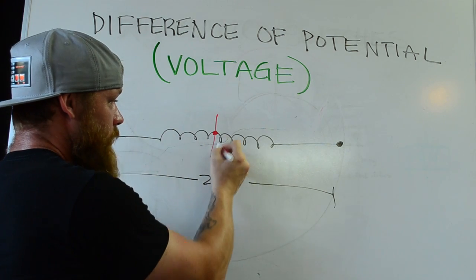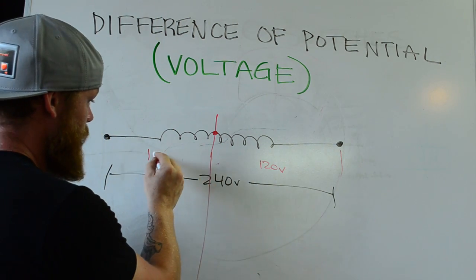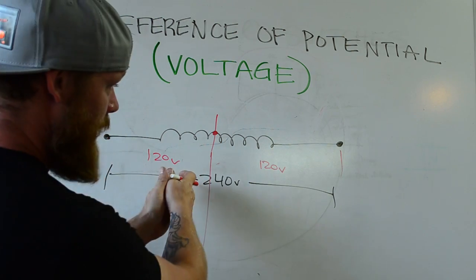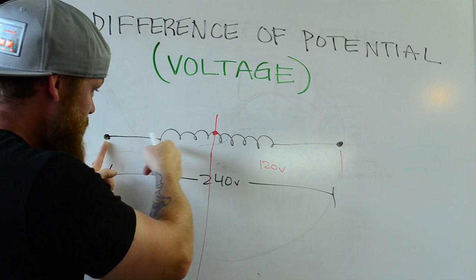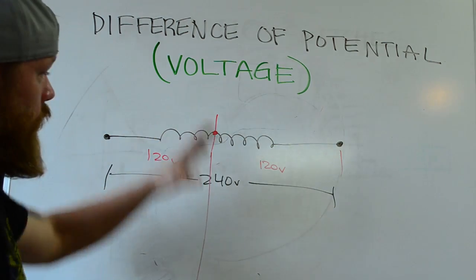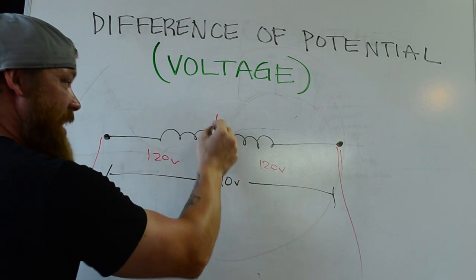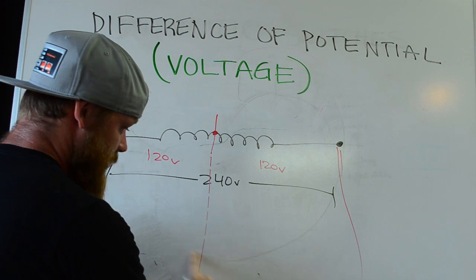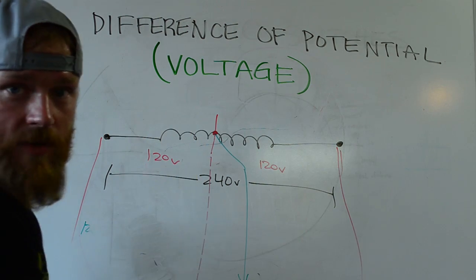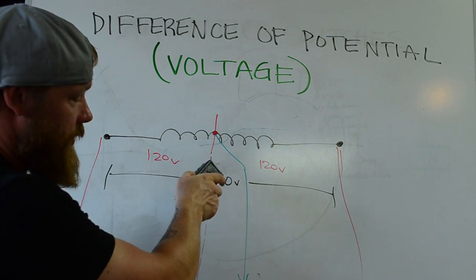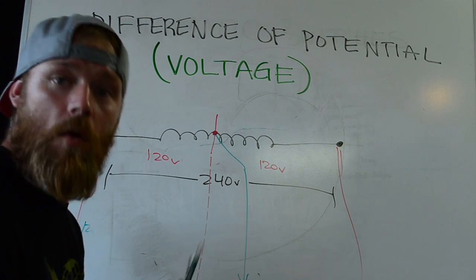You literally make a connection right in the middle of the coil and send it down. So between this part of the coil and the center tap you have 120 volts, and between the center tap and the other end you have 120 volts. If you have a whole coil that's 240 and you test the potential at the halfway point, it should be half — 120 volts. That's how we get 120 volts: from a transformer up there, we're sending one hot down to the house and another hot down to the house, and somewhere in that transformer they're tapping the dead center of that coil and giving us a neutral. That's usually the same point where they ground the poles too, so the ground and neutral are at the same potential even at the transformer. Ground and neutral should always be at the same potential.